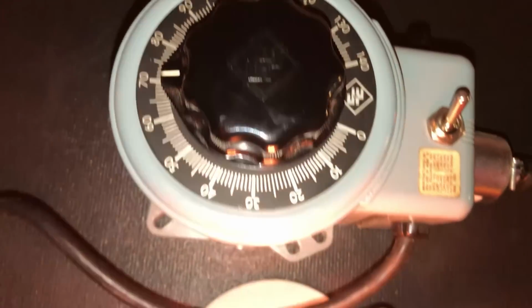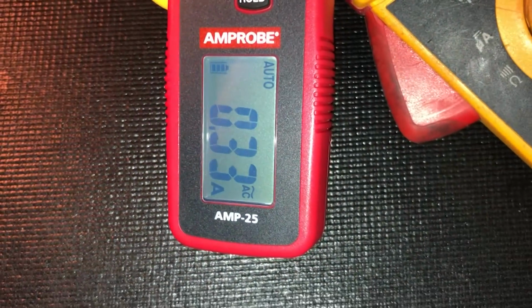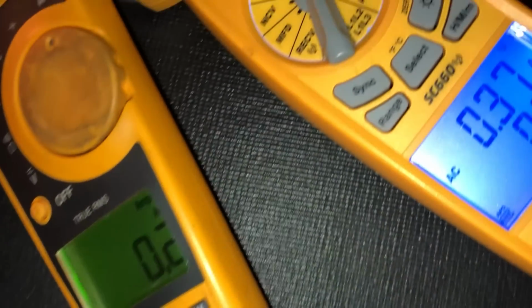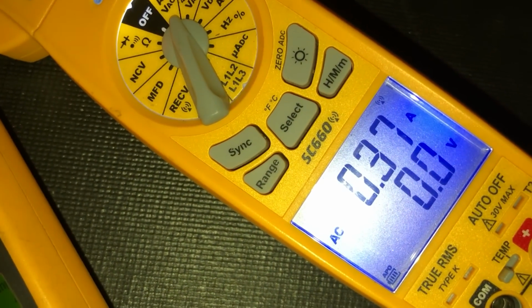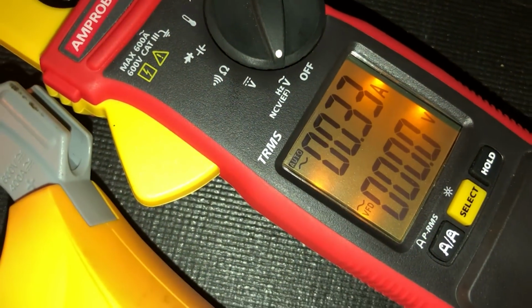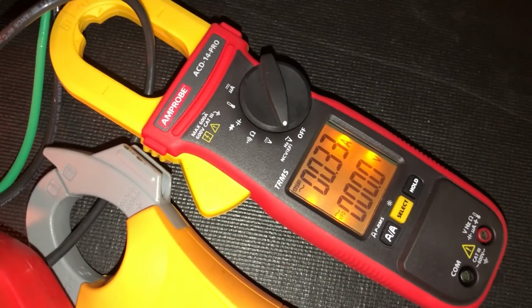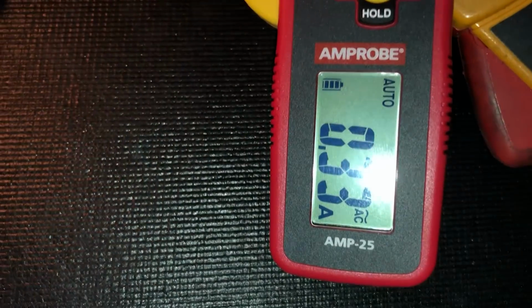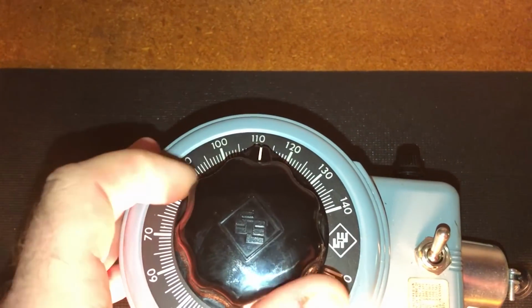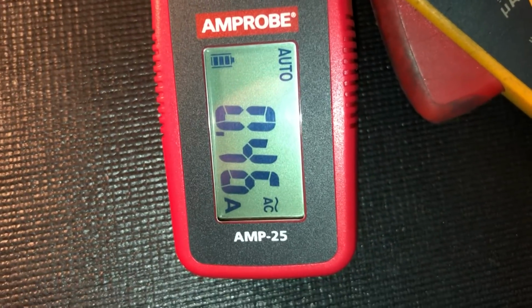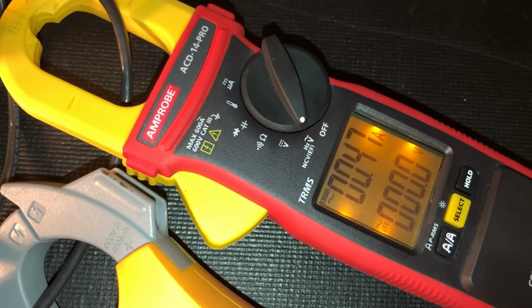With the Variac at about 70 volts AC, we have 0.33 amps detected on the AMP-25, 0.2 on the Fluke 902, 0.37 on the Fieldpiece SC660, and 0.33 on the Amprobe ACD14 Pro, which matches exactly to the AMP-25. Let's jack this up to a typical building voltage of 120, and we're now at 0.45 amps on the AMP-25, 0.4 on the Fluke 902, 0.49 on the SC660, and 0.47 on the ACD14 Pro.